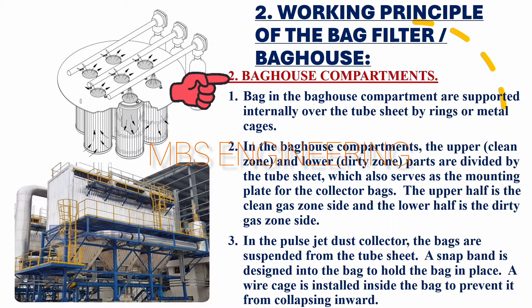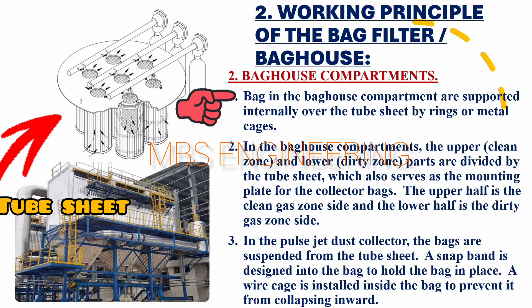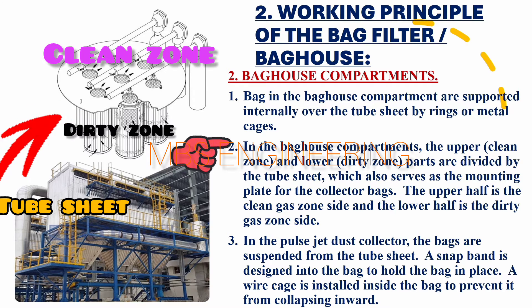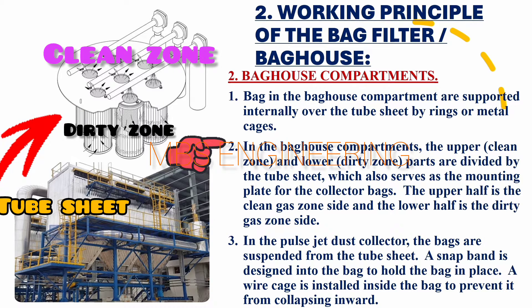Step 2 — Bag House Compartments: The bag in the bag house compartment is supported internally over the tube sheet by rings or metal cages. In the bag house compartments, the upper clean zone and lower dirty zone are divided by the tube sheet, which also serves as the mounting plate for the collector bags. The upper half is the clean gas zone side and the lower half is the dirty gas zone side.